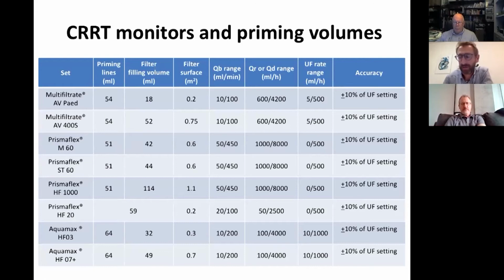And we know that the priming is safe when treating neonates and infants when the extracorporeal volume, that's the summation of the volume in the lines with that from the filter, is lower than 10% of the baby's blood volume. So, for example, if we are treating an infant weighing 4 kilograms with an overall blood volume of 320 ml, the priming should be less than 32 ml. If not, we need to prime the lines with blood, and again, we can increase the risk of sensitization.